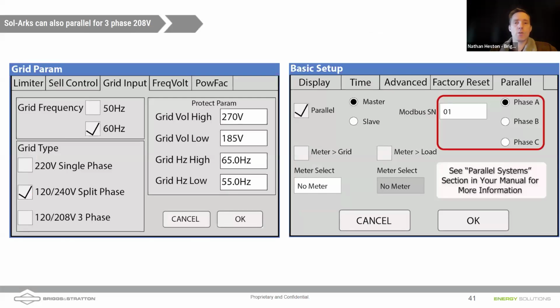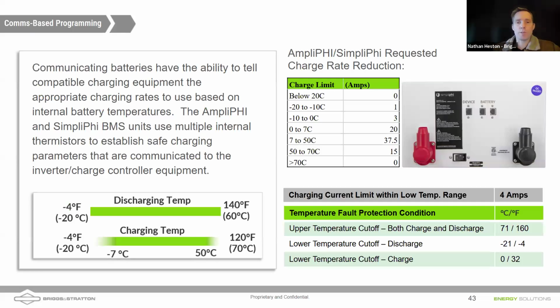And then, of course, in the grid setup here, most of our customers are going to be doing 120/240 split phase. I actually have 120/208 three-phase in my shop here, and you can easily switch the Sol-Ark between accepting 208 leg-to-leg input or 240 leg-to-leg input, right? And so you have those options.